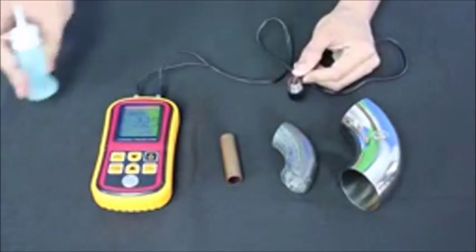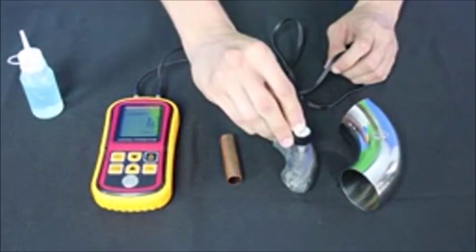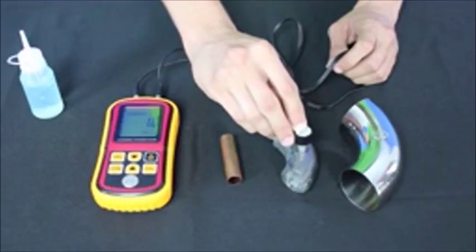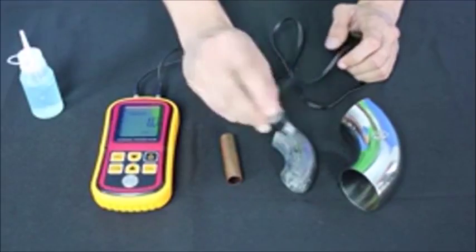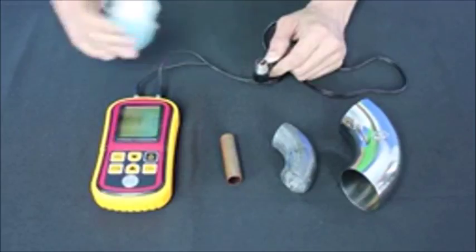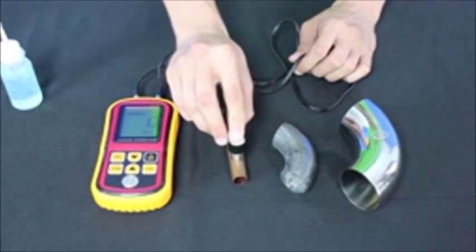There we go. Now that the thickness gauge has been calibrated, let's measure some metals. As I mentioned before, the first thing we want to do is add some gel to the sensor tip. And the next thing we want to do is start measuring metals: 1.2, 3.2, 3.7.